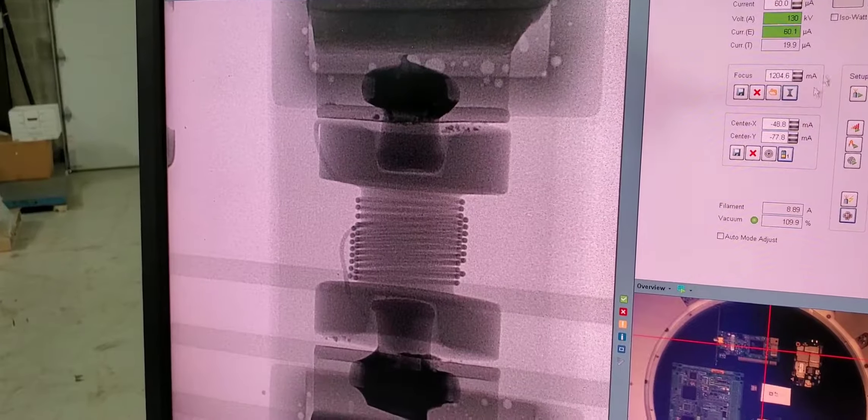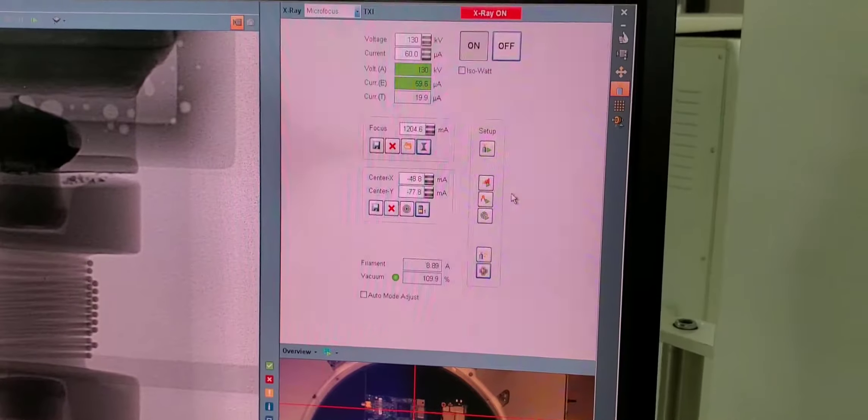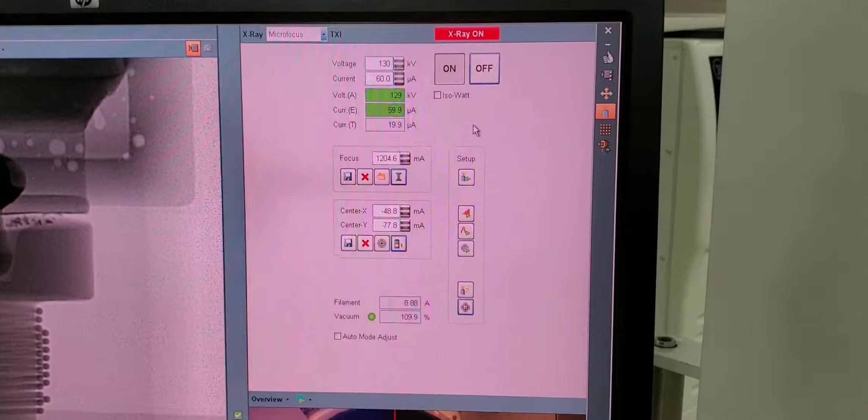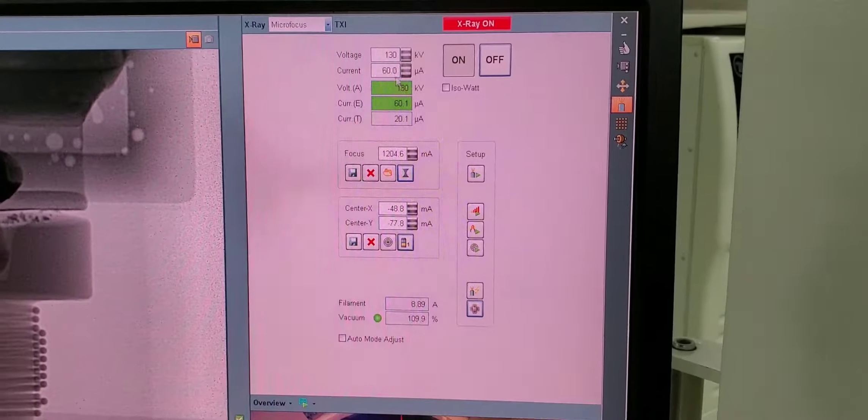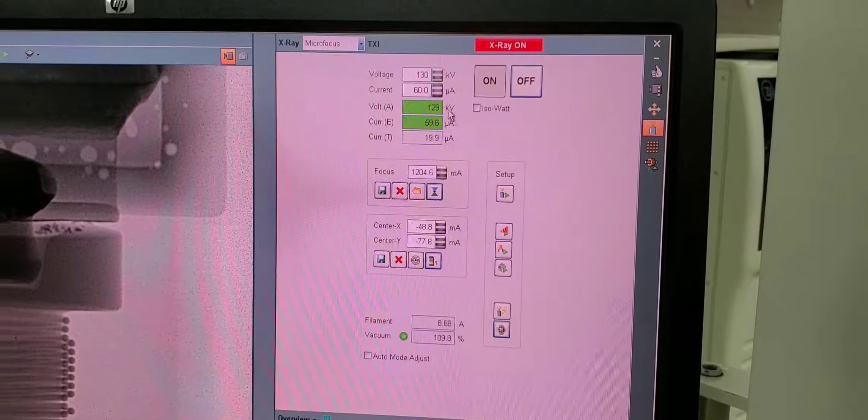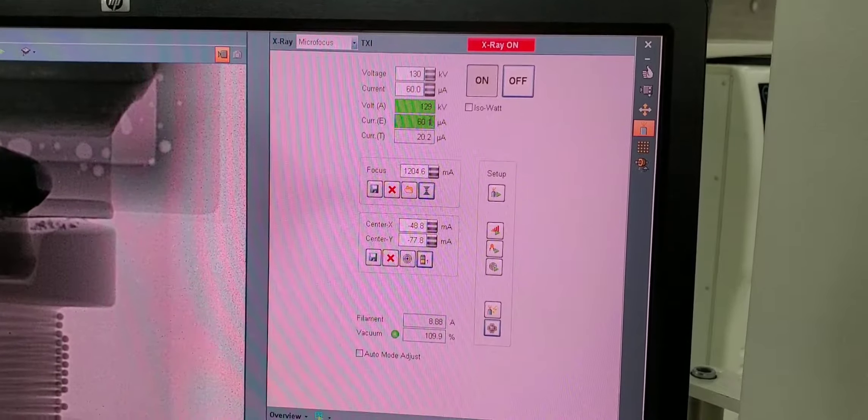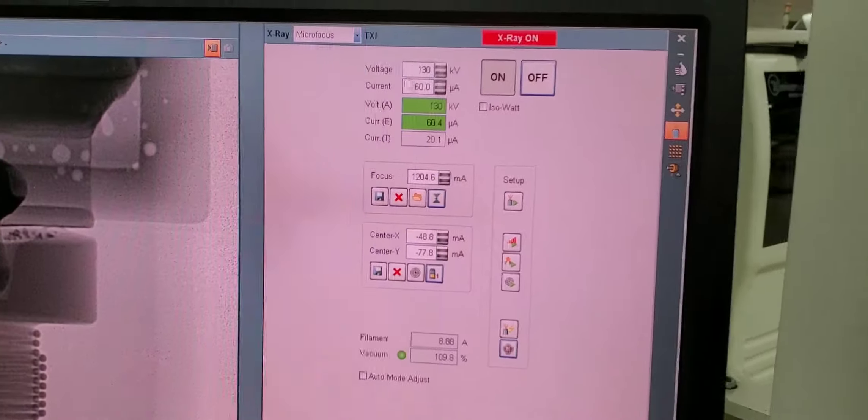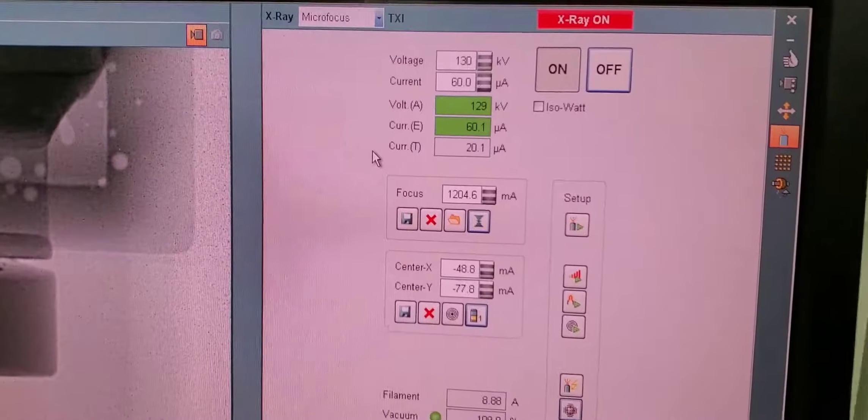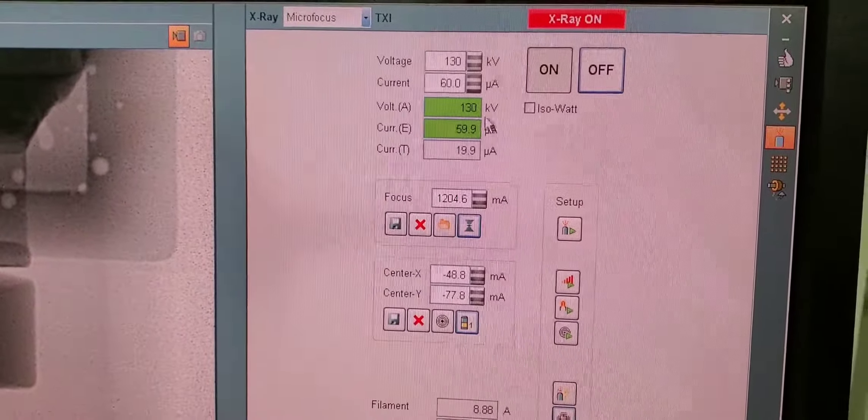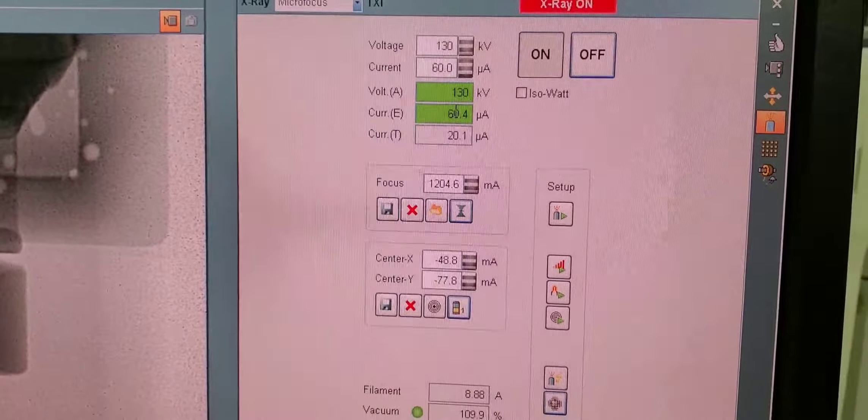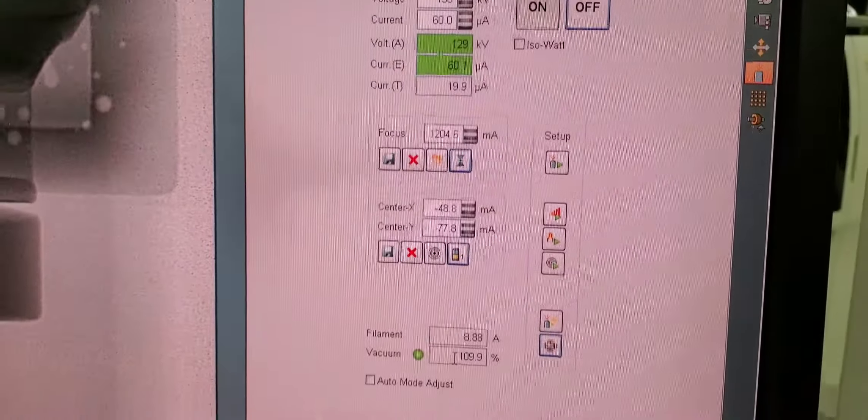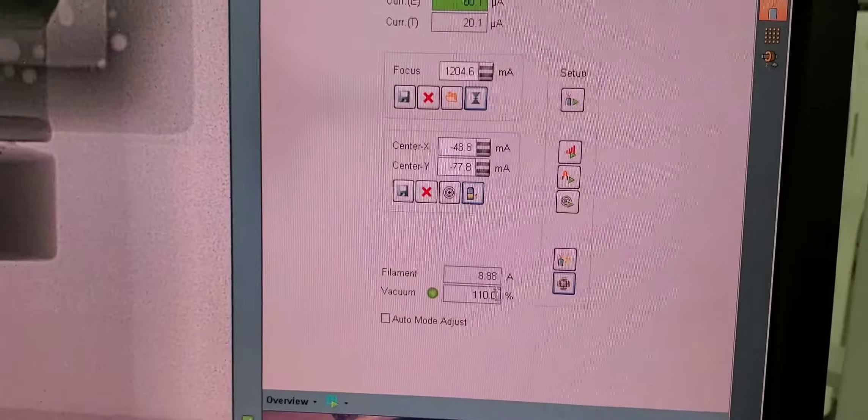Now this over here is the x-ray summary. It shows what power we're set at and what it's actually performing. So we set it at 130 kV, 60 microamps, and this is what it's actually doing. Vacuum level down here.